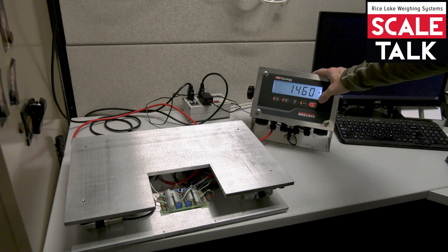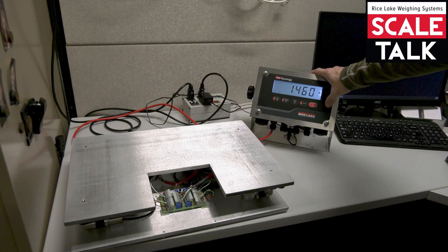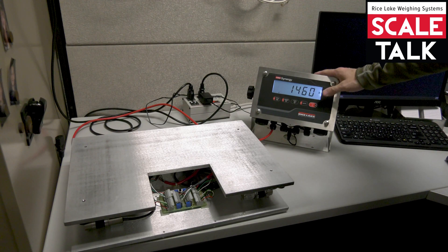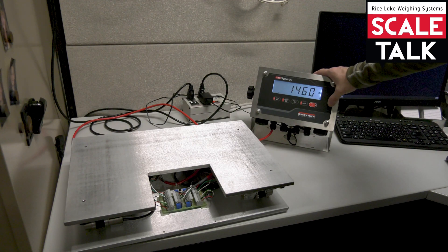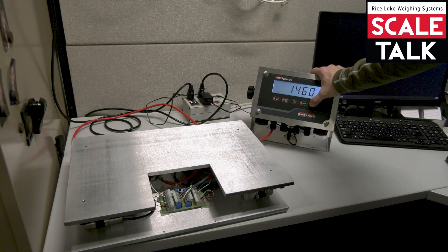What we'll have to do is get into the configuration menu of the indicator in order to perform this, and so to make that happen we have to begin with the scale powered down. So we're going to press and hold the power button until the display reads off.